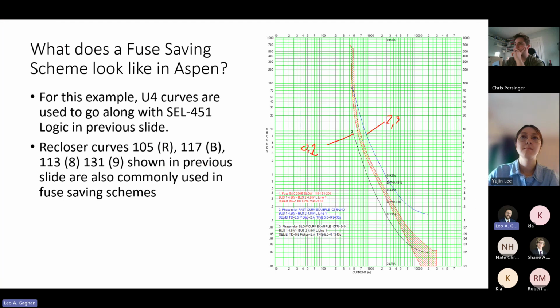So, right, we can see this here. Curve 3 is going to be faster than the fuse. It'll save it. We'll give it 2 chances. Then we're going to swap over to this slow curve. And then, okay, now fuse, you got to take it. You're the guy. We need to continue to feed power to our customers, so you got to take it. And technician stinks, but they're going to have to go out and change that fuse.